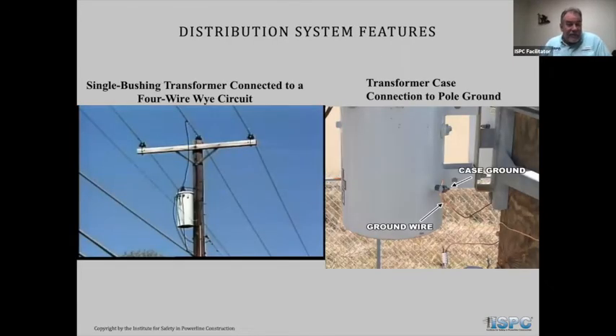Okay. Single bushing transformer connected to a 4-wire Y circuit. It's kind of an older picture, but you can see the neutral at the bottom of the transformer. And we didn't get a real good shot of this, but you can see the communication wires at the bottom, and they look like they're fairly close to those secondary connectors. A single bushing transformer is energized at the top and grounded only through the case ground. That's why we have that picture on the right hand side showing that case ground. If that ground wire is not connected, then that unit will be energized. At what voltage, it's hard to say, but could be as much as 7,000 volts. And the bracket that transformer is hanging on would also be energized.